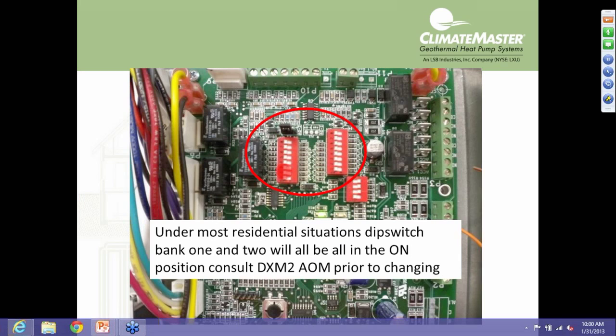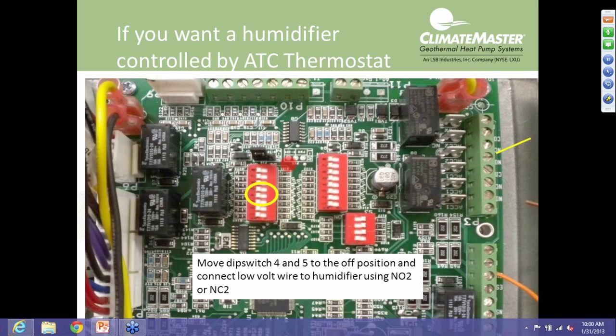Now, bank 2 over here is for if we're going to configure some of our accessories. So again, these you might make an adjustment depending upon what you want to do. For instance, if we want to control a humidifier with the ATC communicating thermostat, we can move dip switch 4 and 5 to the off position, and now we have a dry contact over here on the side where I've got this yellow line for our humidifier. So we can use the transformer and the humidifier, bring in to this terminal strip, and then when the ATC thermostat's calling for humidification, it will then power the solenoid valve for the humidifier and bring on humidification.